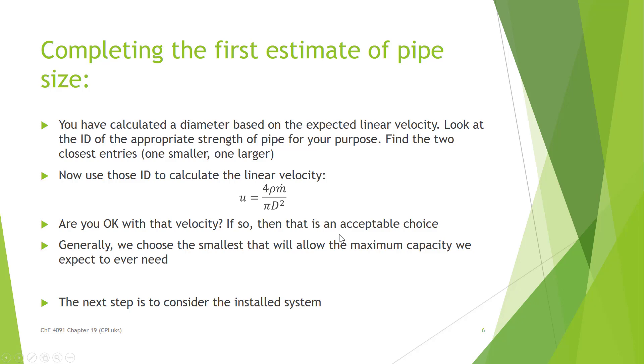Now you've calculated a diameter based on an expected linear velocity. How do you complete this first round estimate? The diameter you calculate probably won't match one of the inside diameters in the standard tables — it just never does. I recommend finding the two closest entries, one smaller and one larger, and using those to calculate what the linear velocity would be, working backwards. Then look at those velocities and decide if you're happy with them. In general, if you're happy with both choices, choose the smaller one — but choose the smallest that allows for the maximum capacity you ever expect to need. This is just our first guess, and most of the time the value doesn't change too much.